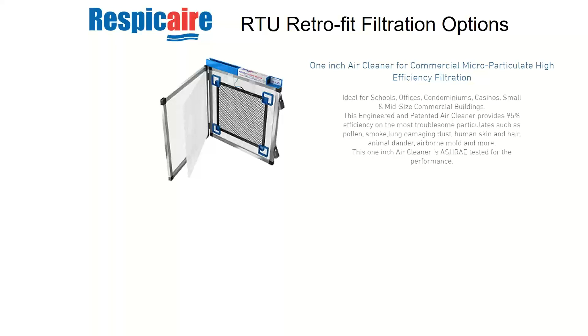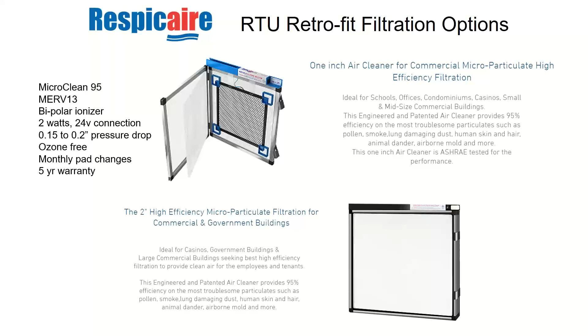If you're restricted and can only put in small stuff, there are ways. Here are two examples to get 1 and 2-inch filters. This company is called Respicaire, though there are other manufacturers too. I'm just using examples of people I've worked with before. They have 1 and 2-inch filters that fit into standard rooftops and even standard residential systems, with fairly low pressure drop. They have a filter media, the white part, and an electrical component working together. This particular one is 1-inch and can get up to MERV 13. It doesn't go as high as the deeper filters because it doesn't have as much depth to work with, but I could still get MERV 13 in a 1-inch, which might work for a rooftop where I only have 1 inch to work with. So there are ways to get some of that done if you need to.